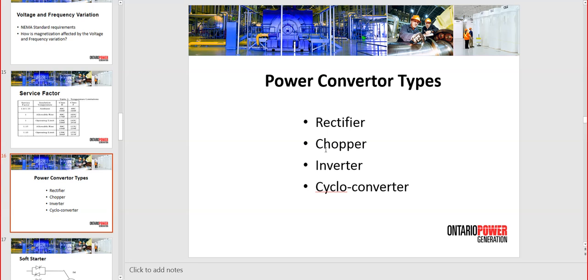Very easy control. Chopper is the same use. If the input is a DC, like in traction, streetcars, subways, and trains, they will have a DC input, so you need to control the DC voltage on the armature of the motor for controlling the speed. Then you're going to have a chopper, because the chopper is chopping the DC voltage, creating variable DC voltage on the output.